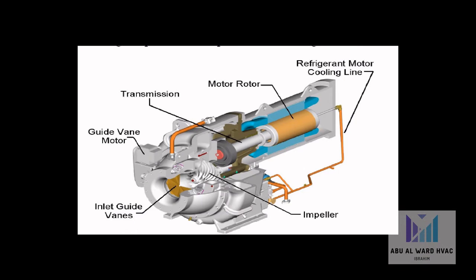Centrifugal compressors use dynamic compression: refrigerant molecules are flung outward by centrifugal force, and new ones are drawn in to replace them. This continuously compresses a stream of refrigerant gas and allows large volumes to be compressed, resulting in a relatively compact-sized chiller. Centrifugal compressors dominate in larger capacities.